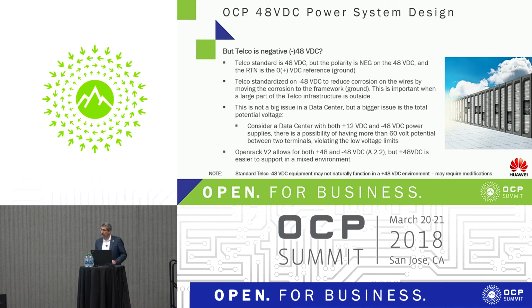But the bigger issue that should be considered is the total potential voltage you might have. Part of the OCP standard is you could have a rack with a 48 volt bus bar vertically in the back, and you could also have a 12 volt bus bar.